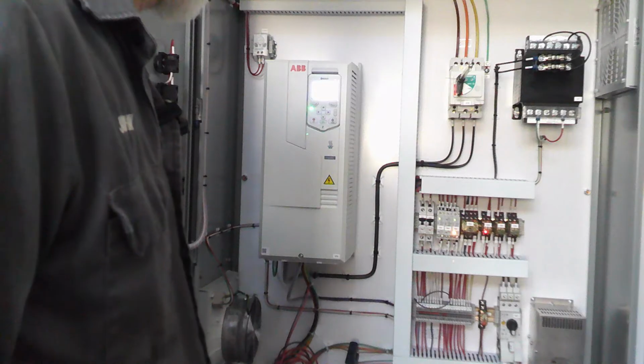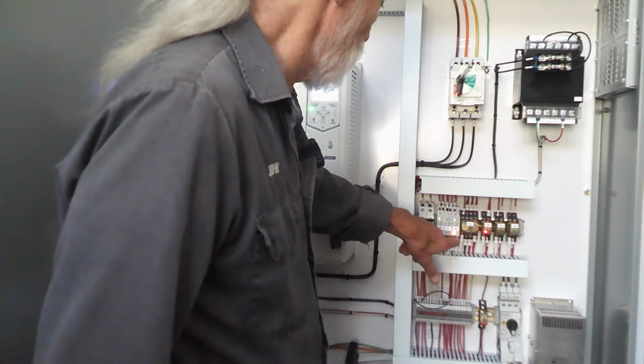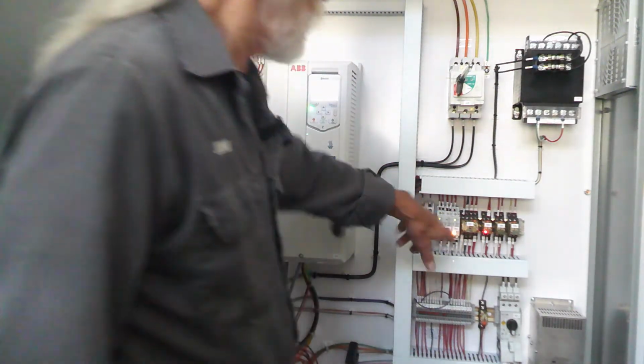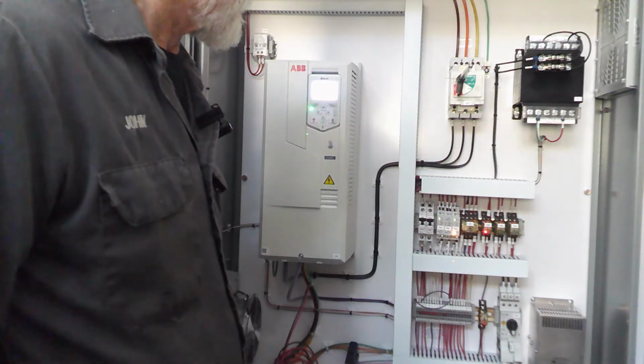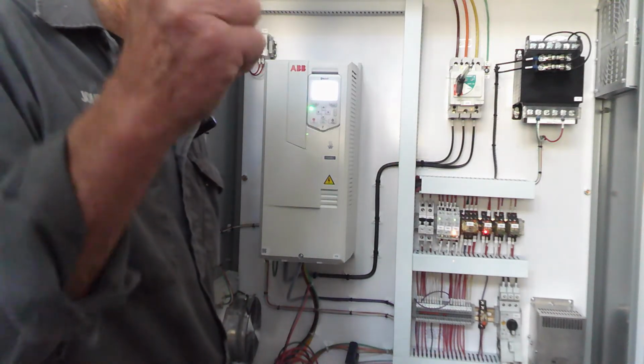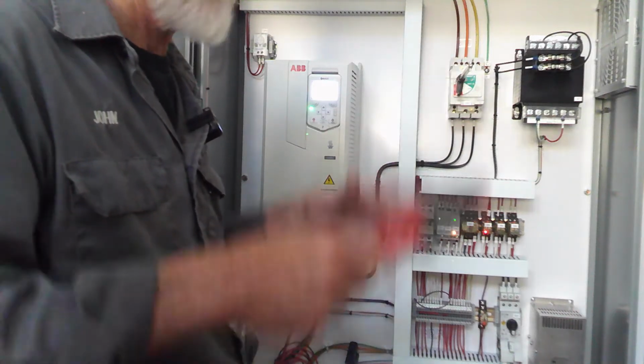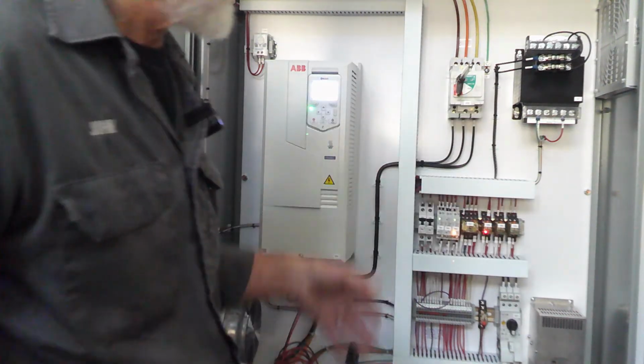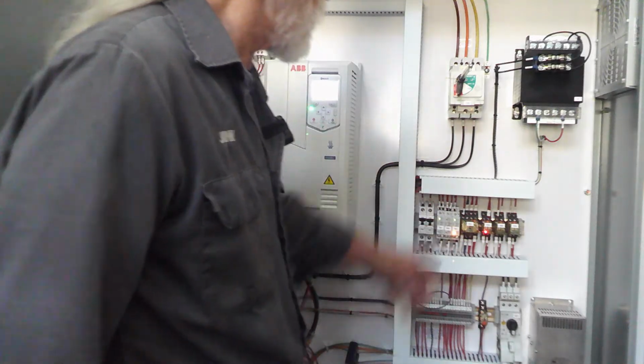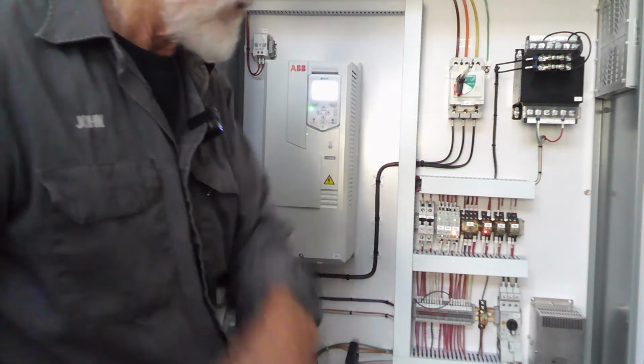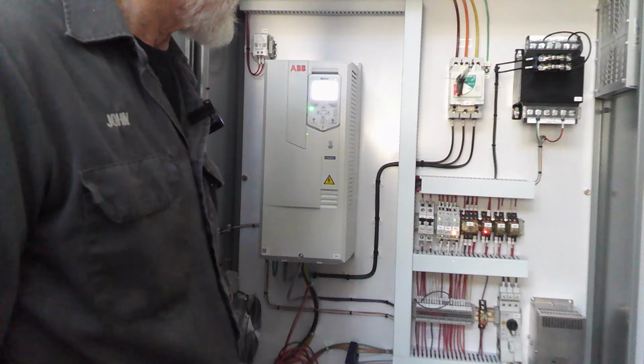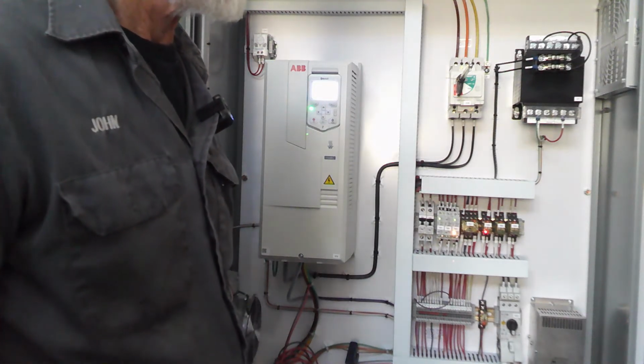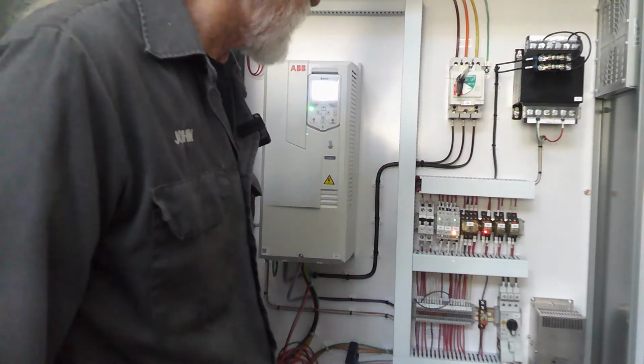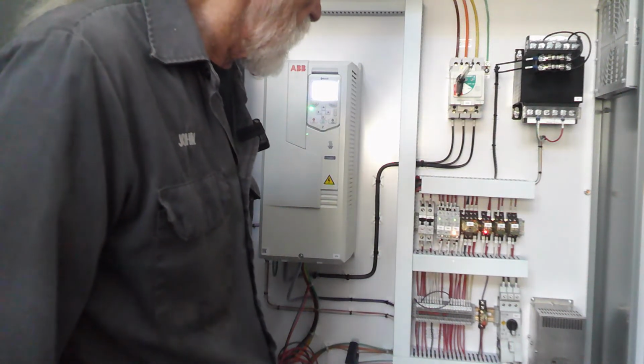Okay, so that's that. Now, what was going on here with some of this stuff: one of these is a time delay that bypasses that photo eye to give the unit a chance to stabilize before it decides whether there's a problem. That's one of them. One of them's the shaker motor, it says on the thing what they do, and that is how long the shaker motor will run. There's a third one which I can't think of at this moment, but I will.